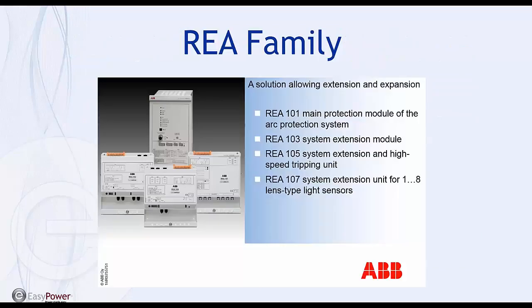So now let's briefly go over the REA family and see what they look like and discuss some of the main features. You have a main unit, which is the REA101, and that provides all the tripping. You have the extension units, the REA103, 105, and 107. The REA105 also has high-speed tripping units, and so it can provide selectivity. That's the main takeaway for the REA105. The REA107 just has lens sensors, and the REA103 has the loop sensors, but it has to pass the light information back to the main unit, so you don't have your selectivity.